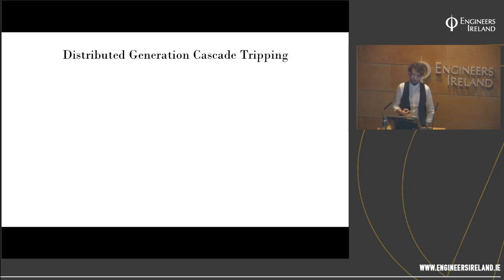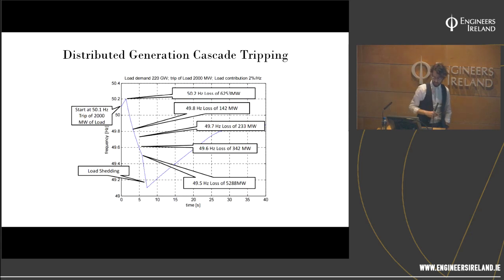And this is okay in small penetrations, but when you get to high penetrations of distributed generation, again, you can have these unintended consequences. So what I'm going to show you is a trip of 2 gigawatts of interconnection in Europe and the resulting frequency response due to the cascade tripping of distributed generation. So you can see you lose the cable, the frequency increases. At 50.2, you have a cut of solar panels, and because there was such a high penetration of, well, this is a simulation, but because there's a high penetration of PV, the frequency falls significantly.